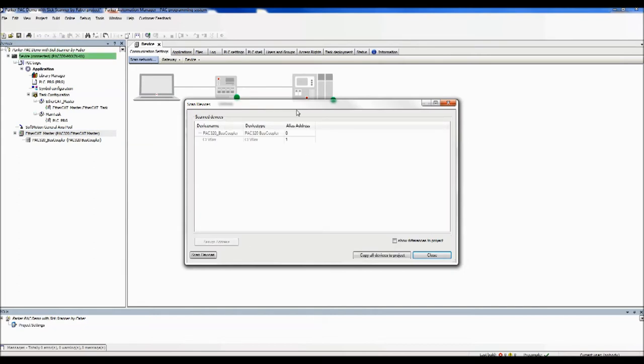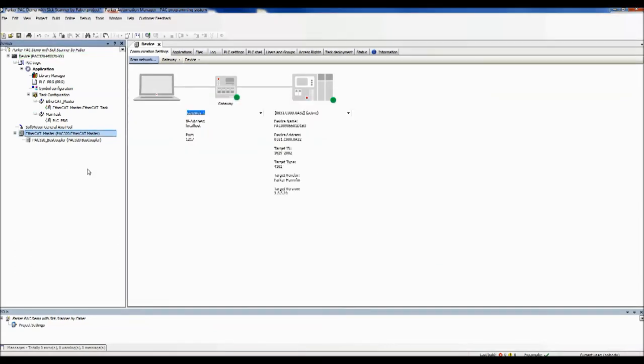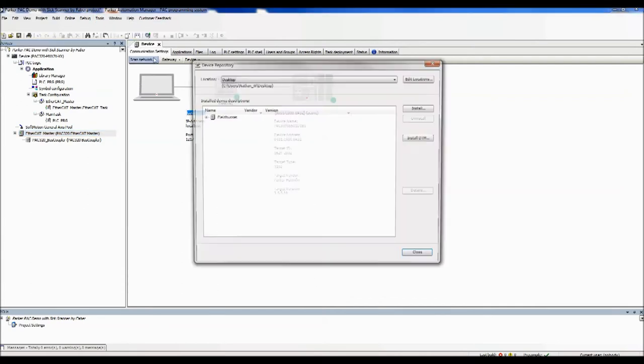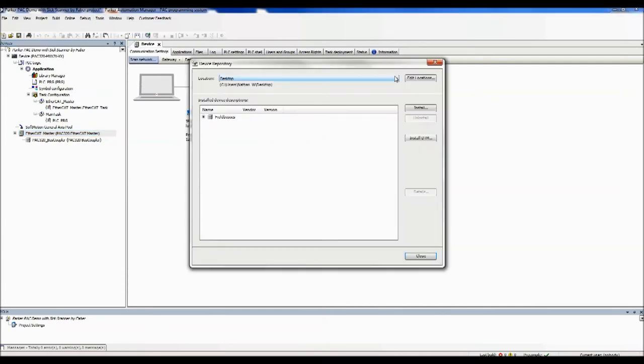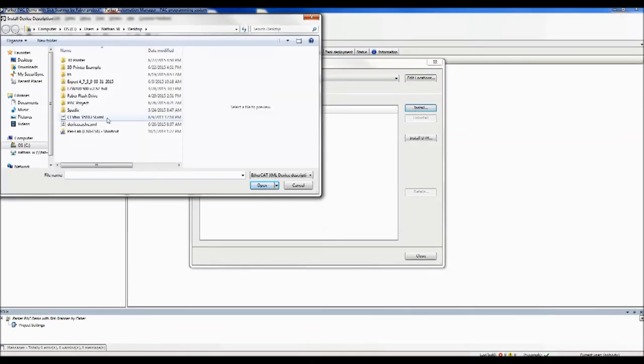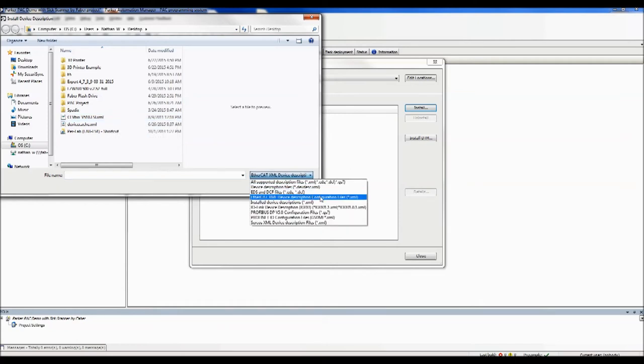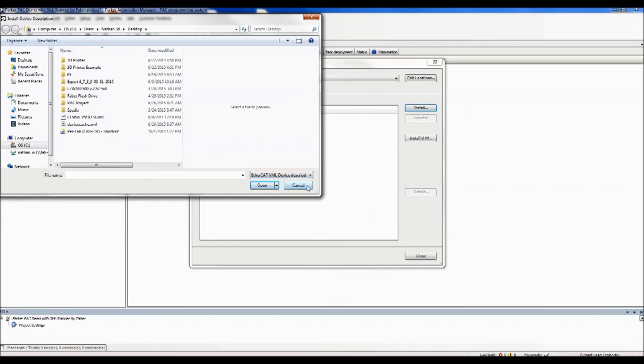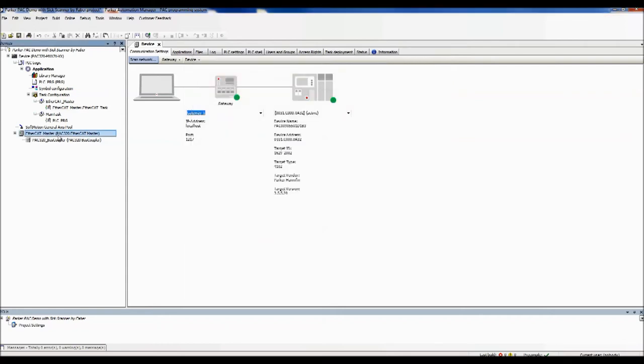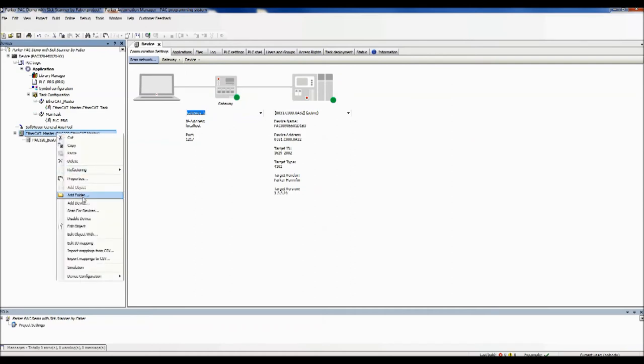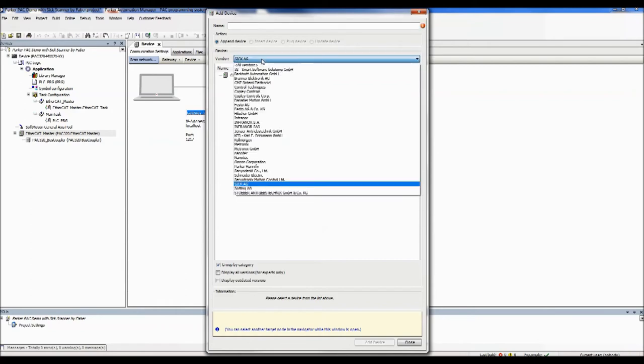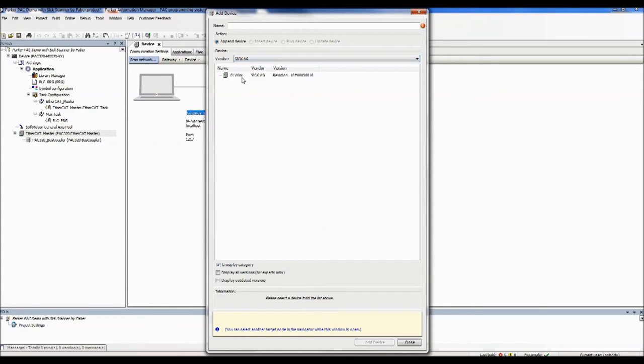I've already built one of these before, so if you've already configured a system and put in the proper files, it'll appear right there. I'm going to close this and show you how to add that in. So if that doesn't appear, you want to go up to Tools, and you've got to add the device to the device repository. And you'll go to Install, and you'll want to have the .xml file for your particular device. And make sure that you select the EtherCAT .xml device description configuration file. If you select something else, it won't work properly. And so then once you do that, you can drill down, and there will be this particular one. So you can close that, and then in order to add it, you add device, and you can either do the entire list, or you can sort by vendors. And there's our device right there.